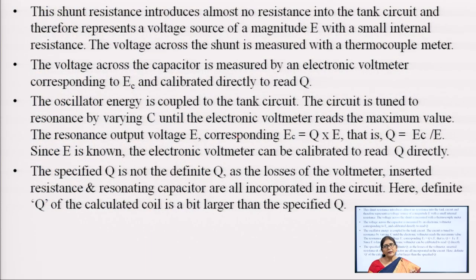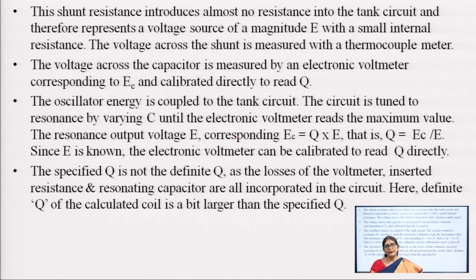The value shown by the meter includes all values — the capacitor value and the source resistance — so it incorporates the circuit Q also. The displayed Q may be less than the actual Q of the coil or capacitor.